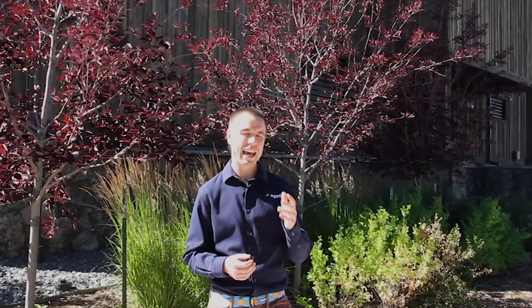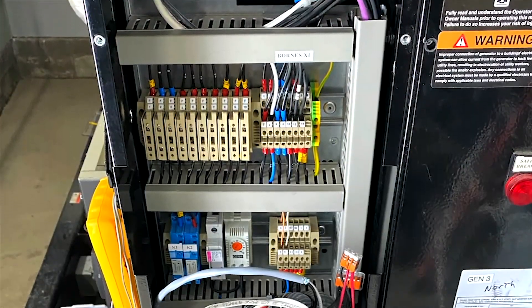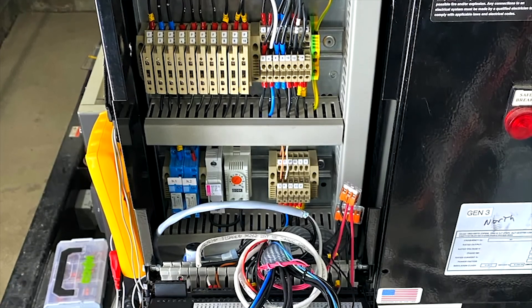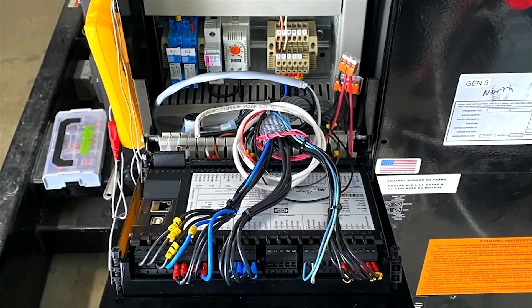The DEIF AGC150 really simplified the retrofit, because it had everything built into a single box. It fit in the hole that was already there from the old controller, and it had the governor control and AVR control all built in, along with the paralleling and synchronizing capabilities we required in the system.